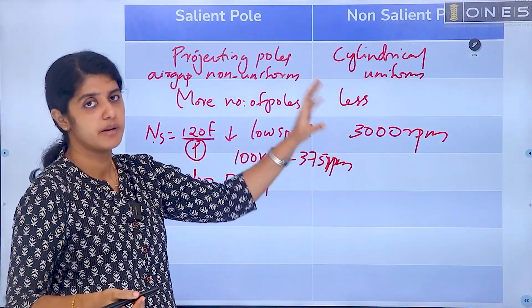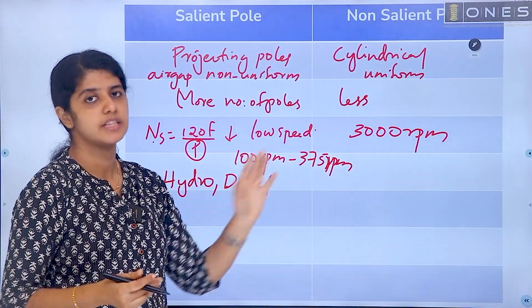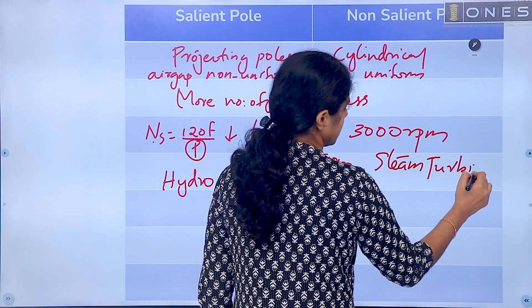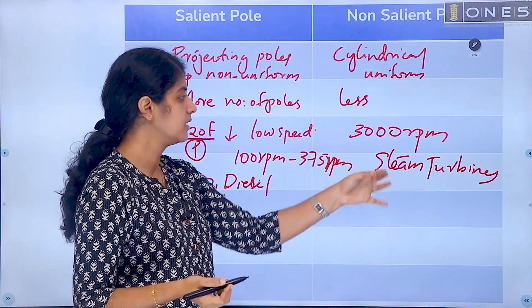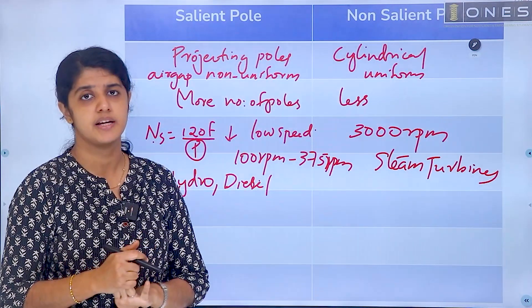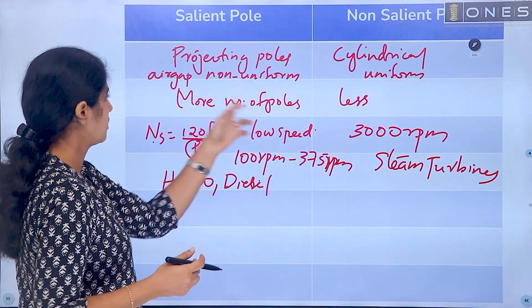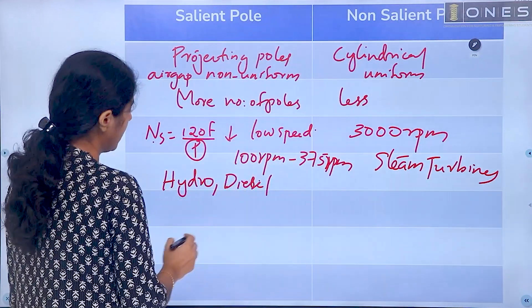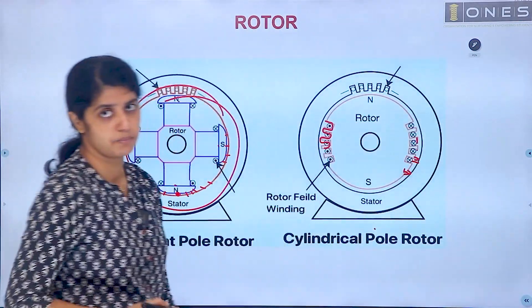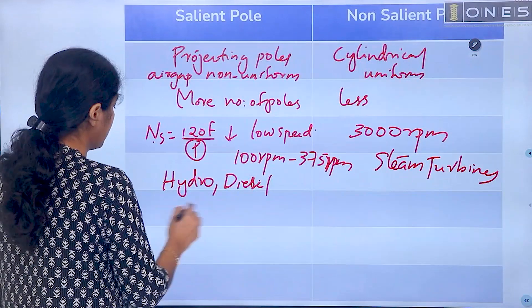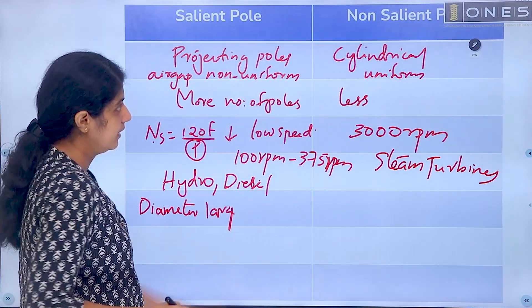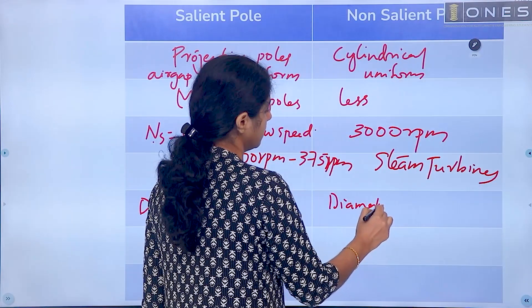For example, in a thermal power station, you will see the cylindrical structure because steam turbines are used. Steam turbines operate at high speed, so the non-salient (cylindrical) rotor is used in thermal plants. Now, comparing the physical size: in the salient pole, the diameter of the rotor is large, whereas in the non-salient pole cylindrical rotor, the diameter is small.